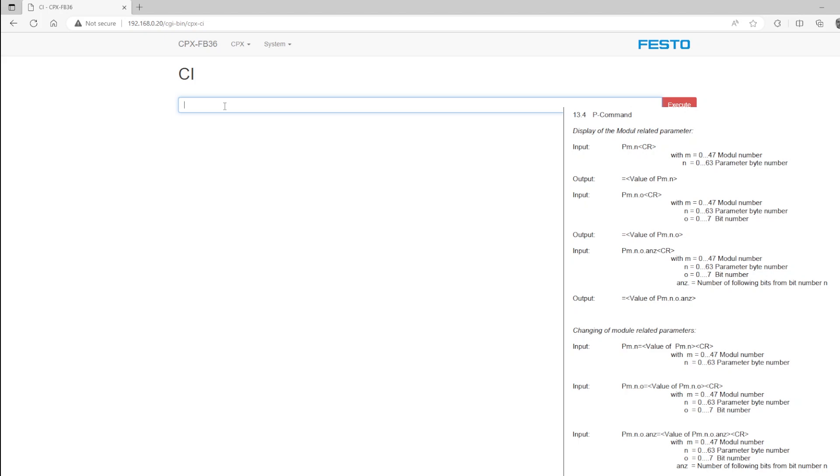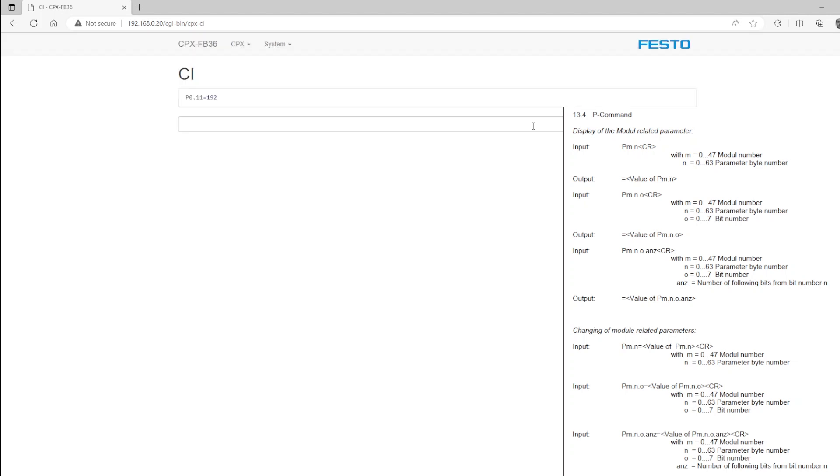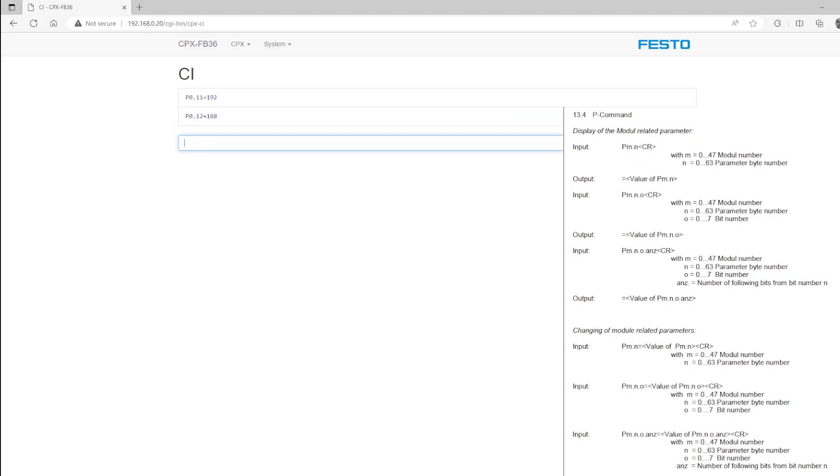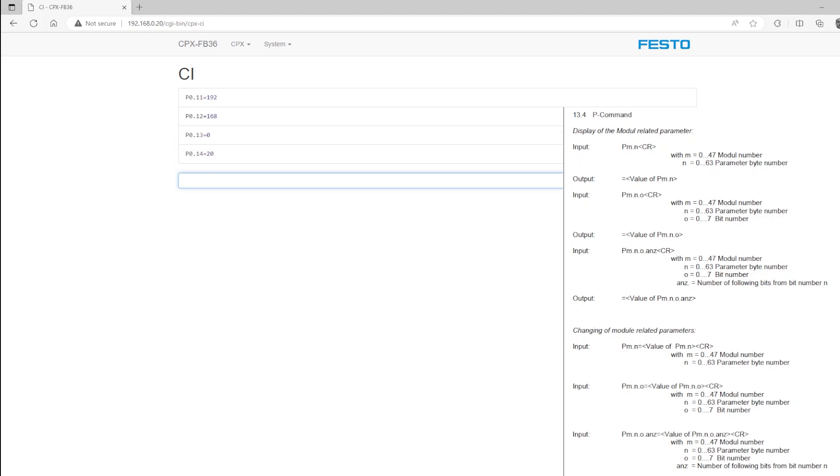And by some trial and error, I've determined that the IP address is between parameters 11 and 14. So I'll check and see what my current IP address is by typing these in. You will get a warning to say, be careful, this is only for experts, and you can acknowledge. There's the IP address of my current FB36 module.